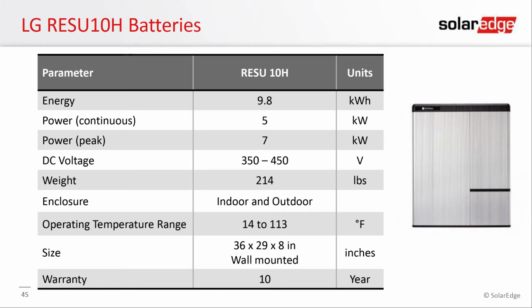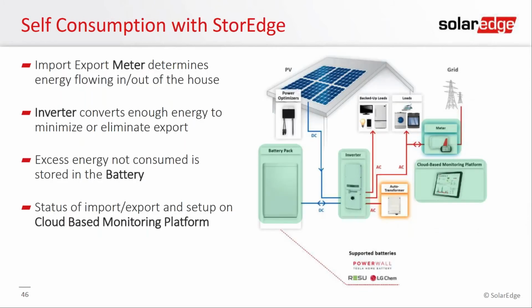It weighs 214 pounds, so it's pretty heavy, and make sure it's a team lift. It's rated to 14 degrees all the way up to 113 degrees Fahrenheit. It's a NEMA 3R enclosure, so if your environment suits, you should be able to install that outside, and it is warranted for 10 years.